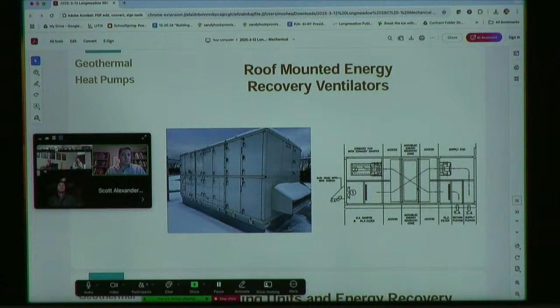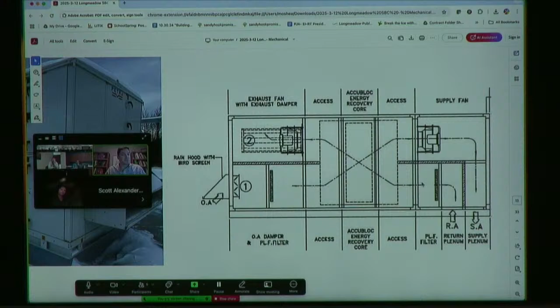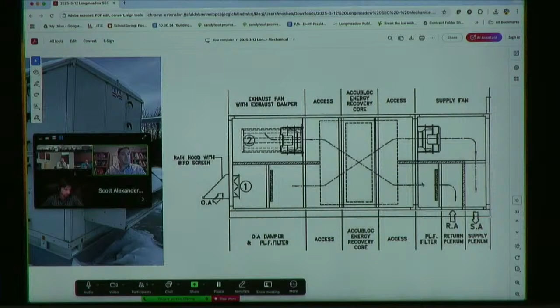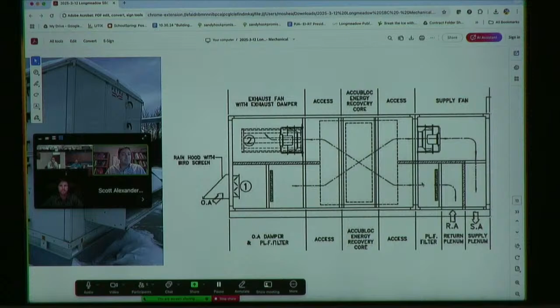Basically, these units have, probably hard to read, but in the very center there, an AccuBloc energy recovery core. It's a dual core that basically continually flips airflow to and fro through the core. So essentially it's continuously exchanging energy. And it exchanges both sensible energy and moisture, so heat and moisture is exchanged. These dual cores are extremely efficient. They're like 85+% efficient at exchanging ventilation air, which is why we don't have any conditioning within the units typically. A lot of that can be done at the heat pump itself.